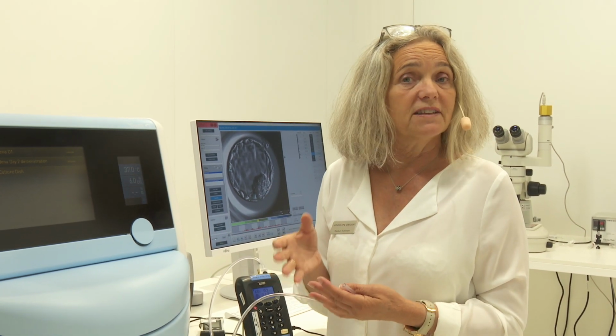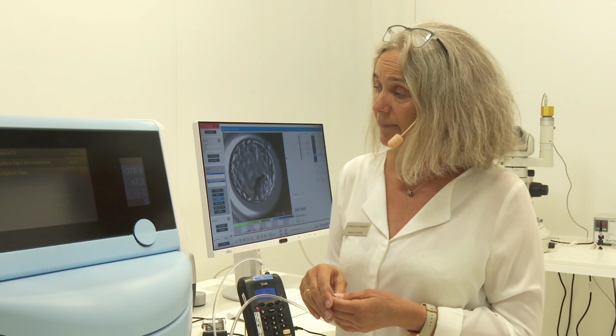The frequency with which you should do validation of your gases should be according to what is described in your standard operating procedures, of course. But Vitrolife recommends this be performed at least every 14 days. So now I'll start with the gas analyzers.